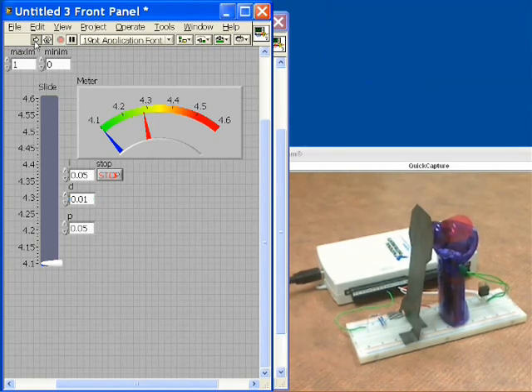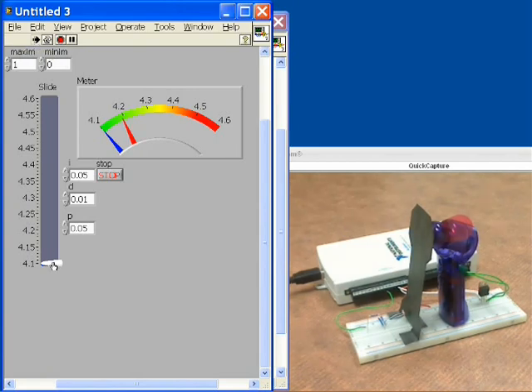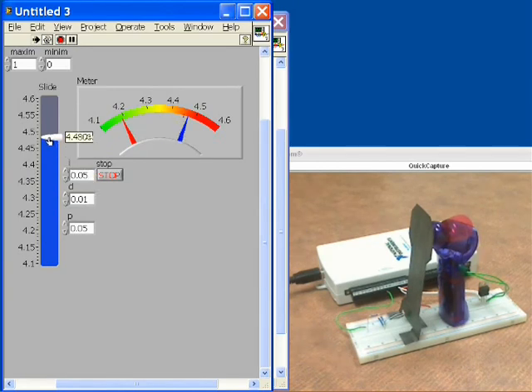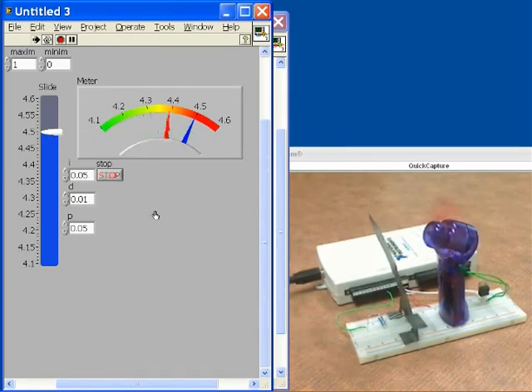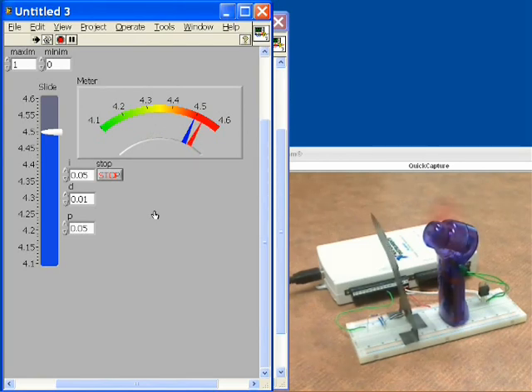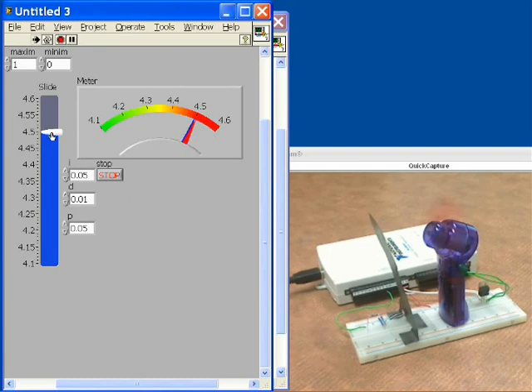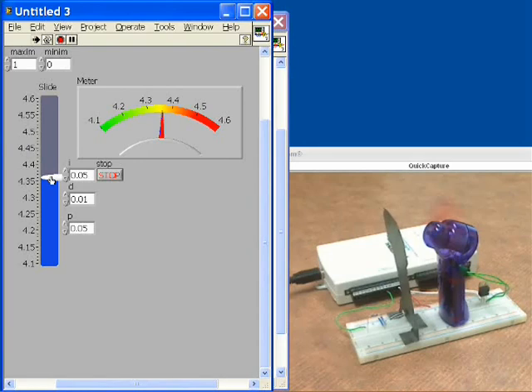So at this point we see the deflector default value is at 4.2 and we're below that so it can't go any lower than that. We're going to take our set point up to about 4.5 and we'll let it stay there. And at this point the deflector will begin to move and it seeks the value. It knows it's outputting just a little too much now so it'll let off and it zeroes in on that 4.5 pretty accurately. Let's go ahead and drop it down to about 4.35 or 4.4 in that range and then we'll see that the fan decreases. It zeroes in and it holds it pretty accurately there as well.